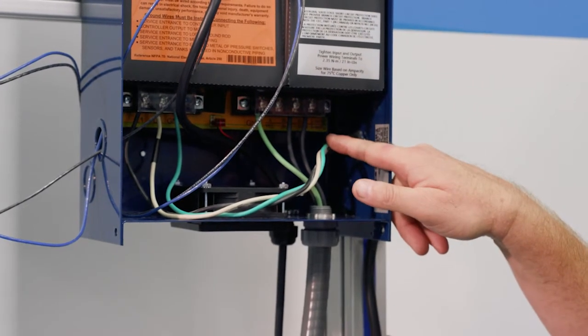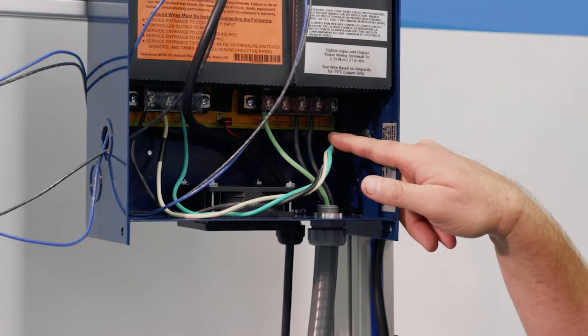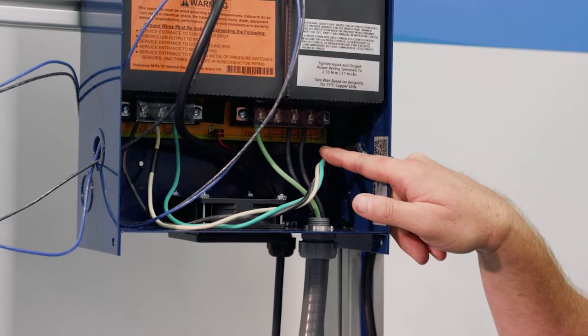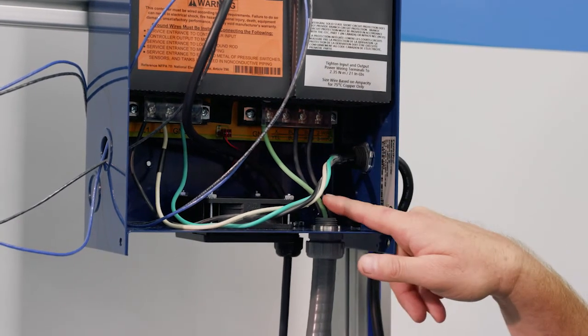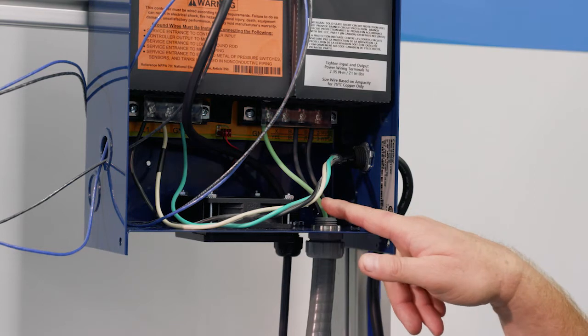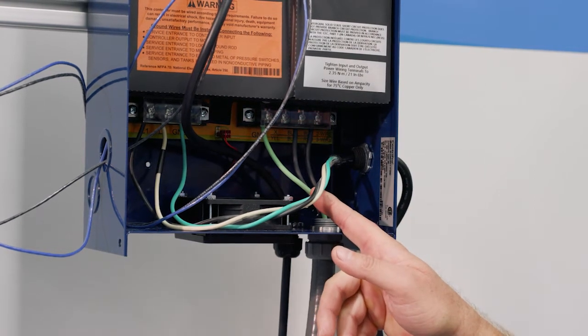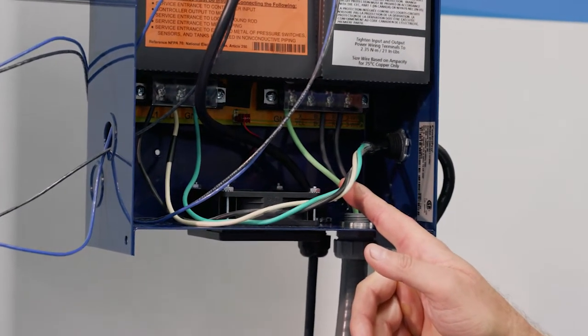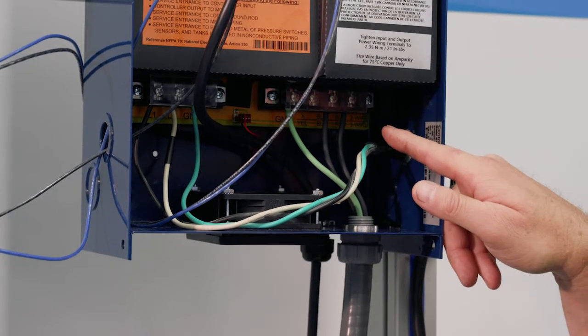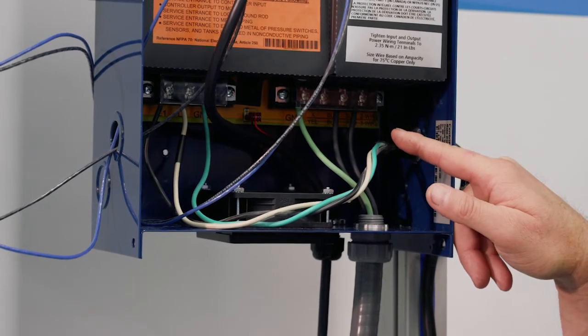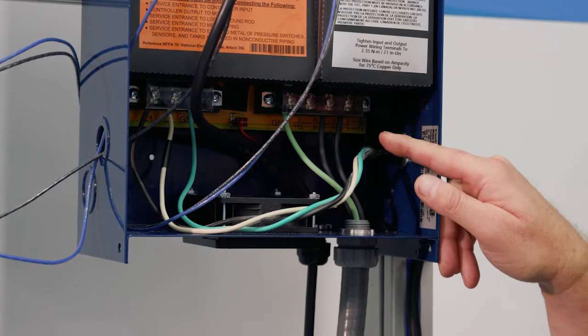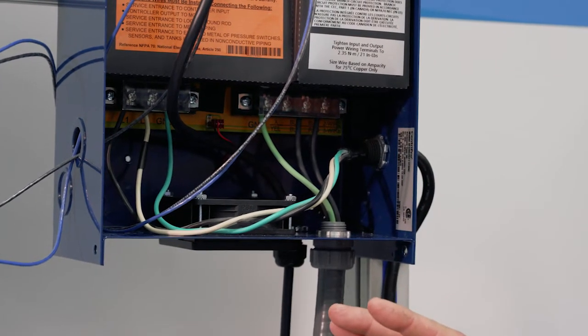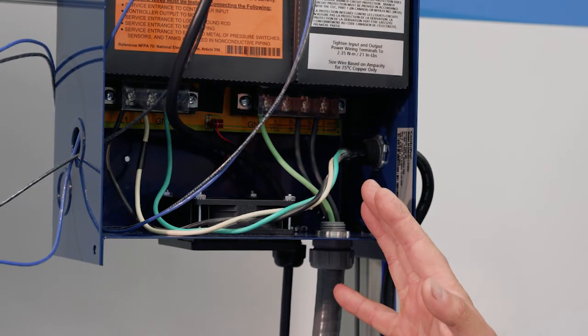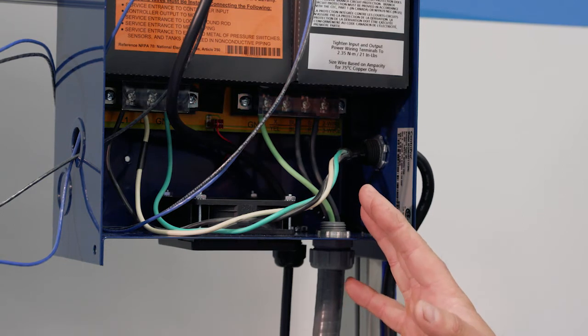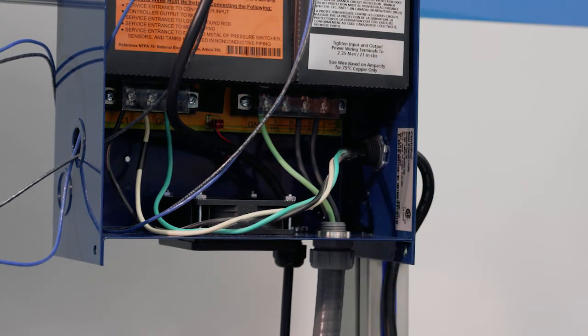So if we look down here, we can see that the 1AS15, you can use that on a two-wire motor, which is what we have here, two blacks and a green. Or you can use that for a three-wire motor, which would have a yellow, black, and red. So it's all color-coded there. But in this case, we're using a two-wire motor, and both pumps are the same.